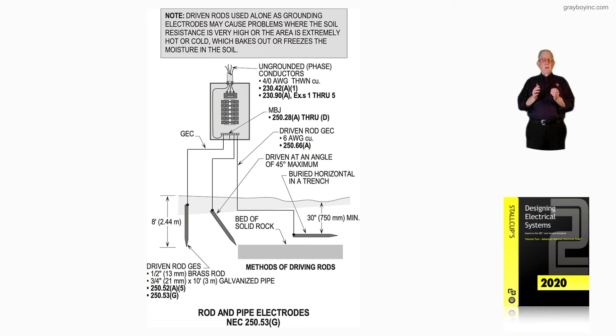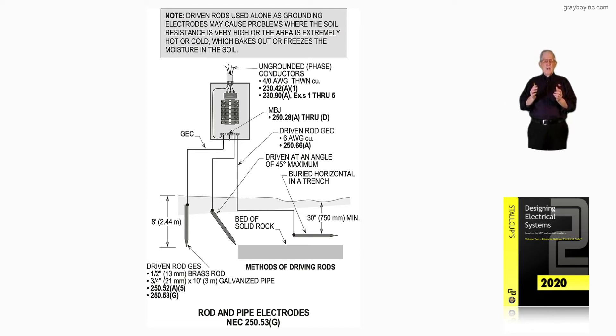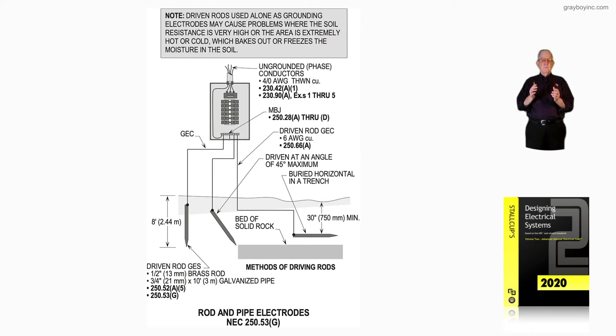250.4A5 says you cannot use the earth as a path for the fault current solely. You could connect to ground there, as stated in 250.54, as an auxiliary grounding electrode. And if it's a driven rod, that's how you're using the rod in this case.